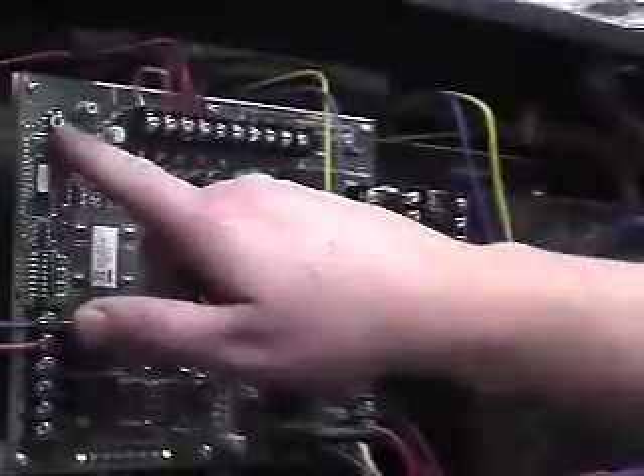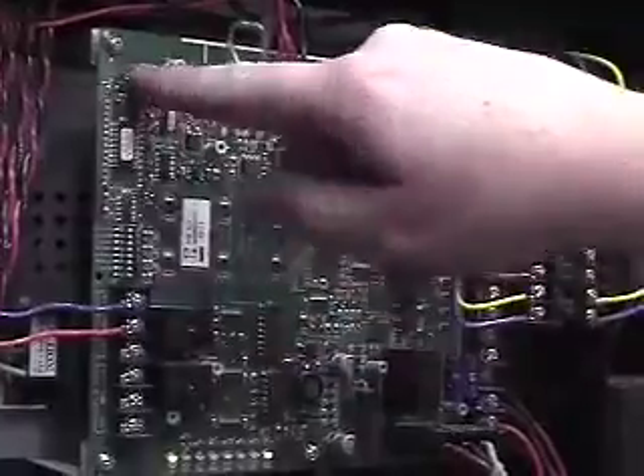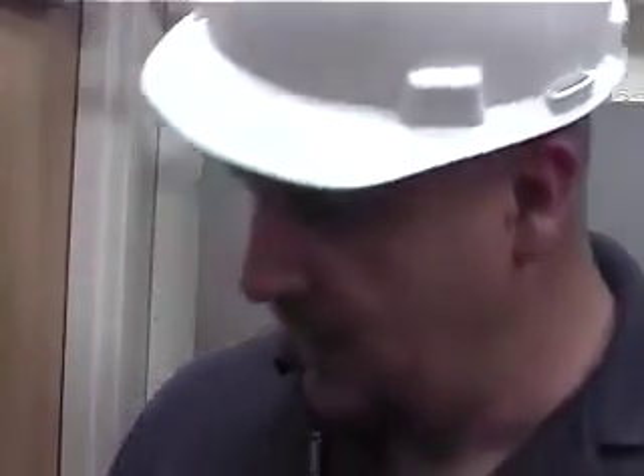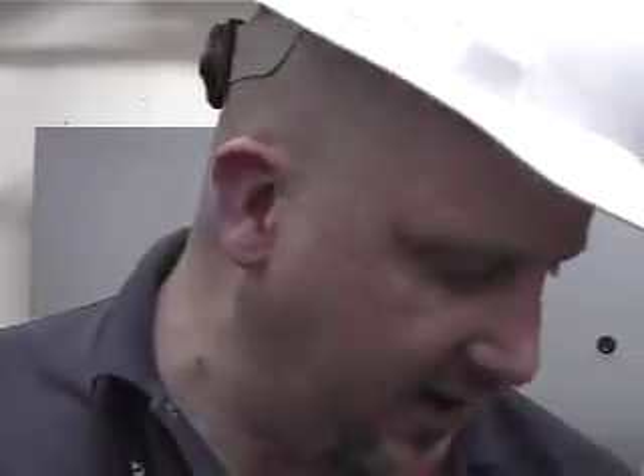To clear that blinking light, there's just a little reset button here that you press to reset the power supply, and it goes through and clears out that blinking light. So that's kind of a nice feature. I don't know if it was a UL feature, because I know the UL 9s changed some stuff, and that's when these came out with the new UL 9. So that could be a feature that they put in on the UL 9s, but I'm not sure because I haven't seen any of our competitors' new power supplies. But that's a nice feature for intermittent faults on the circuit.